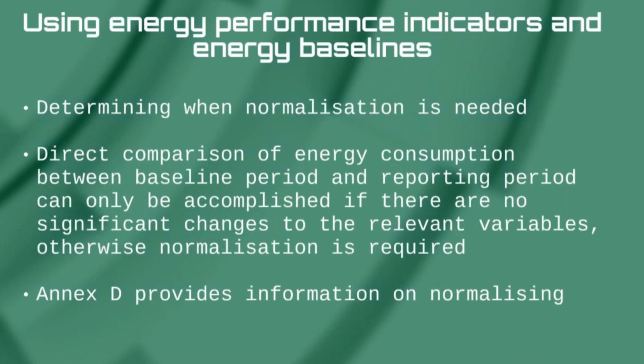Direct comparison of energy consumption between a baseline period and reporting period, or even from year to year, which you might be doing as well, can only be accomplished if there are no significant changes to the relevant variables. Otherwise, normalization is required.